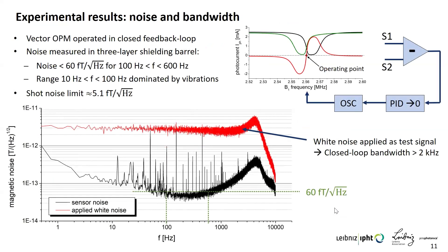We also measured noise and bandwidth. The OPM was operated in a feedback loop so that the operating point is always fixed, and the noise was measured in a three-layer mu-metal shielding barrel. The noise was better than 60 femtoteslas per root hertz in the range between 100 Hz and 600 Hz, going down to below 50 femtoteslas at some frequencies. Between 10 Hz and 100 Hz the noise is dominated by vibrations of the shielding barrel, so the intrinsic spectrum could be better. The shot noise is around 5 femtoteslas per root hertz. The bandwidth in closed-loop operation is about 2 kilohertz.